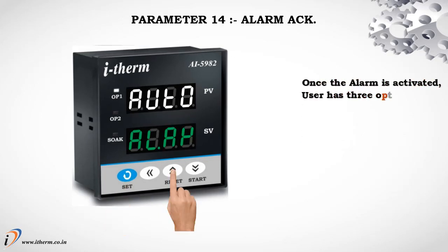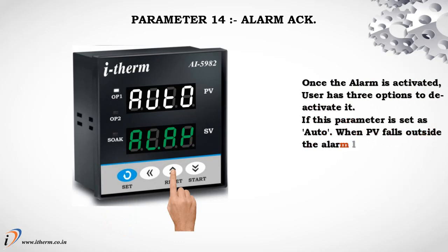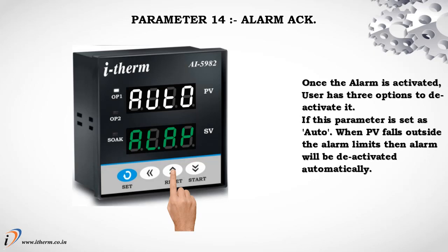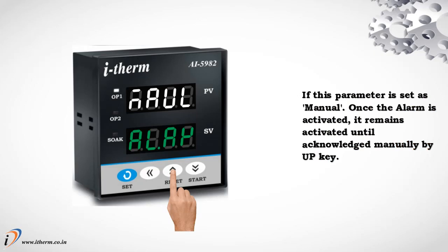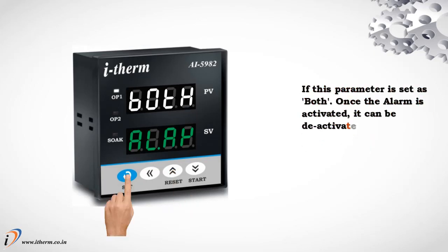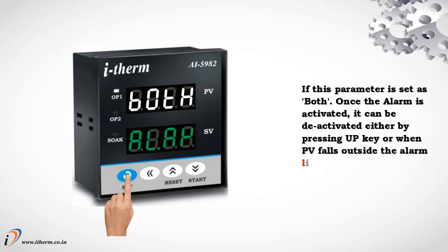Parameter 14: Alarm Acknowledged. Once the alarm is activated, the user has 3 options to deactivate it. If set to Auto, when the process value falls outside the alarm limits, the alarm will be deactivated automatically. If set to Manual, once the alarm is activated, it remains activated until acknowledged manually by pressing the Up key. If set to Both, once the alarm is activated, it can be deactivated either by pressing the Up key or when the process value falls outside the alarm limits.